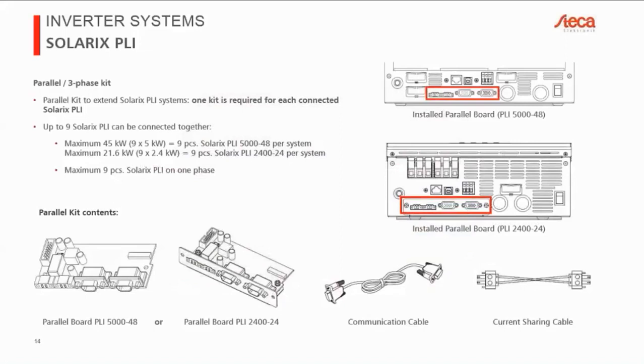So what if 5 kilowatts is not sufficient, or in a 24 volt system if 2.4 kilowatts is not sufficient? For the SOLARIX PLI, you can extend them. Basically, what you need is what we call a parallel kit. It's actually a parallel or three-phase kit because you can use it either for a single-phase system or for a three-phase system. You need one kit for each SOLARIX PLI that you intend to connect together. So you can use 2, 3, 4, up to 9 inverters together in a single synchronized system.